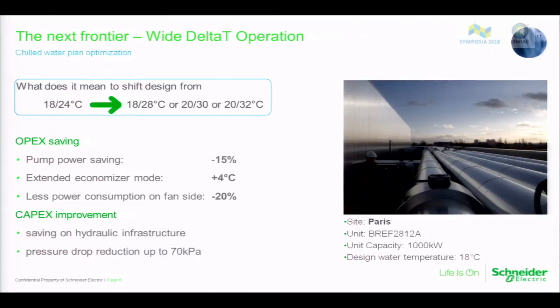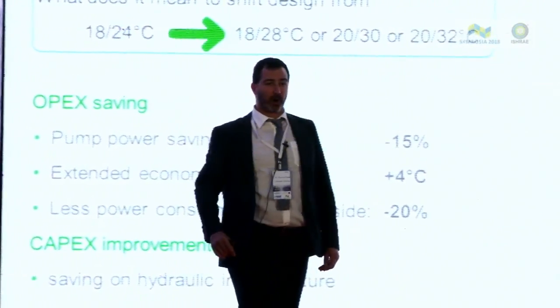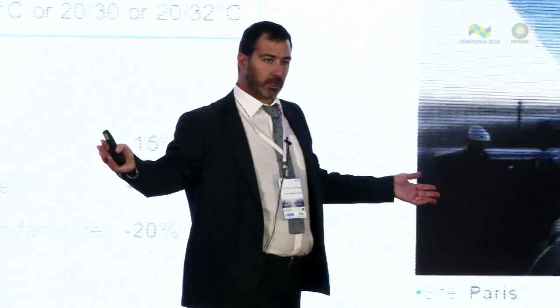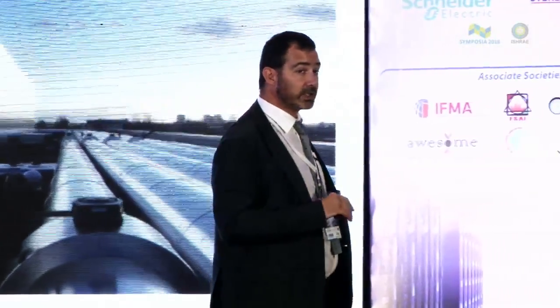Then, the other story is, once we design the maximum water temperature, what is the maximum delta T on the water? Because if the data center is designed to work at 25, 26, and the delta T is 14 on the internal air side, it is possible to consider to not operate with the usual delta T of 5, 6, that is usual for the comfort cooling machine, but to stress this, to operate up to 10, 12 in some cases, of the water delta T. Of course, not all the chillers are capable of this. It is necessary to have a specialized chiller for that, but the more we increase the delta T, the less we have in water flow. And less water flow we have, less piping we have, less size of the piping, less power consumption.